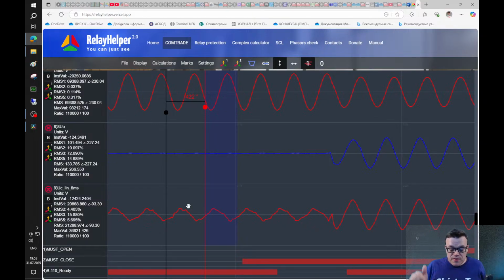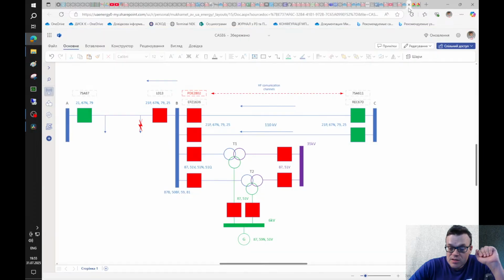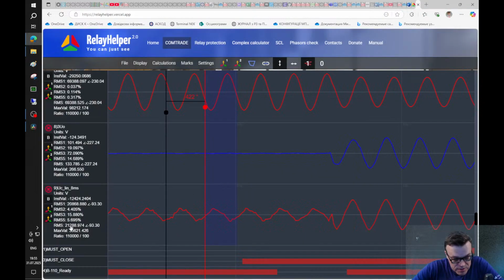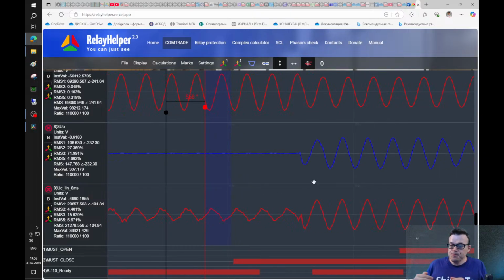But the problem was that no one expected that only one generator would work on the fault and on the load, and that the voltage level would be so low, because you can see that it is around 21 kilovolts, but the setting was around 35 or 38 kilovolts. So we received that non-synchronous reclosing, and I can't say that this is an incorrect setting, because such a type of event was not put in any calculations.